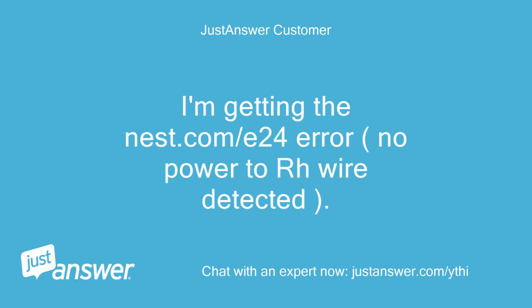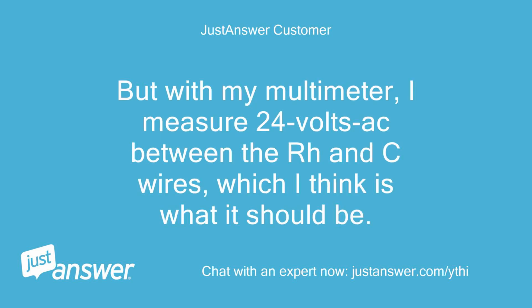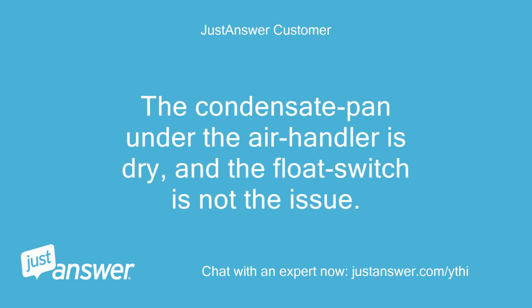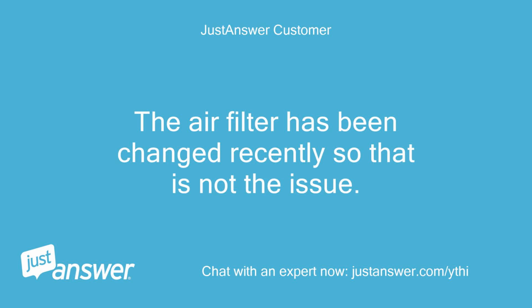I'm getting the nest.com/E24 error, no power to RH wire detected. But with my multimeter, I measured 24 volts AC between the RH and C wires, which I think is what it should be. The condensate pan under the air handler is dry, and the float switch is not the issue. The air filter has been changed recently, so that is not the issue.